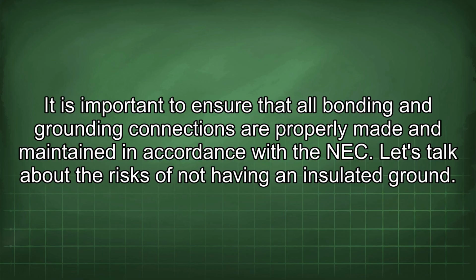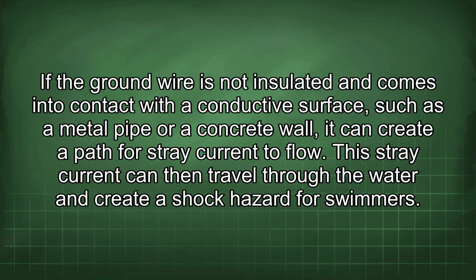Let's talk about the risks of not having an insulated ground. If the ground wire is not insulated and comes into contact with a conductive surface such as a metal pipe or a concrete wall, it can create a path for stray current to flow. This stray current can then travel through the water and create a shock hazard for swimmers.